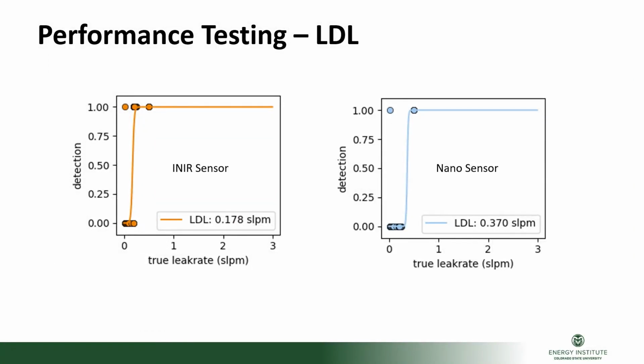So for the first one, we just did limit of detection, or lower detection limit. And we're going to break this down into two sensors. Originally, we intended to use the nano to correct back the INIR. Didn't quite work out, so we just treat them as two independent sensors in the same device. So really, it's like we're testing two high flows. And so we see a lower detection limit of 0.18 liters a minute for the INIR and 0.37 for the nano, which is in tune with the relative performance of their specs.